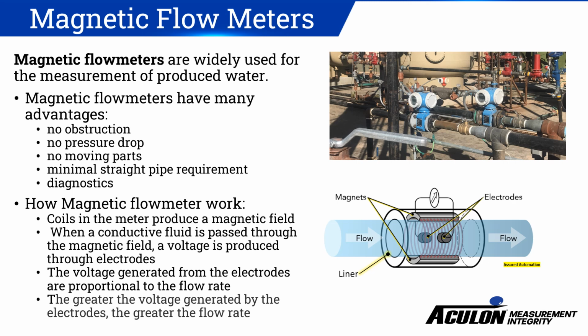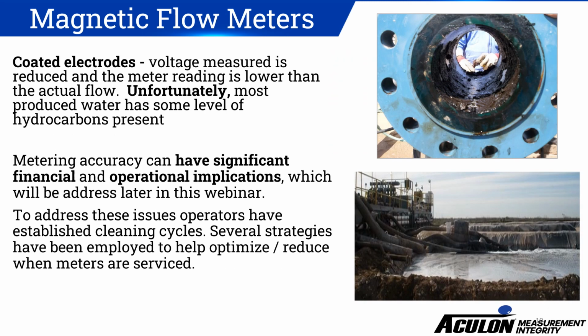that I just discussed. One of the challenges of using magnetic flow meters in produced water is that they can become coated. You can see here on this picture that there is a hydrocarbon coating that coats not just the electrodes but the actual tube itself. If the electrodes become coated or insulated from the flowing fluid, the voltage measured by the electrodes is reduced and is no longer representative of the actual flow rate. This means that the meter is reading lower than the actual flow.